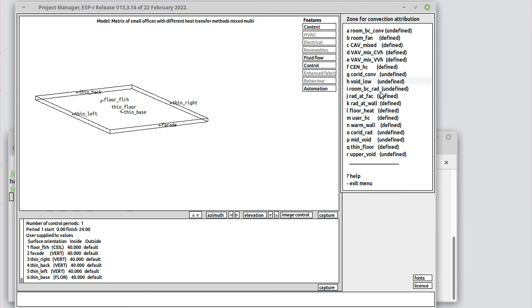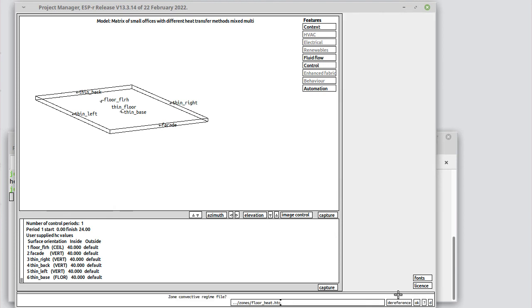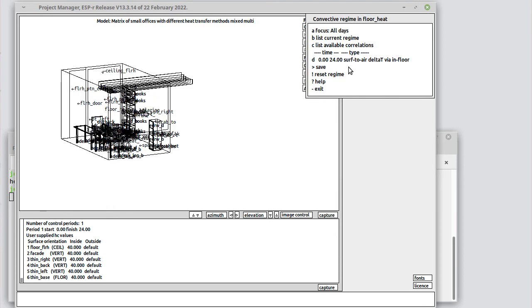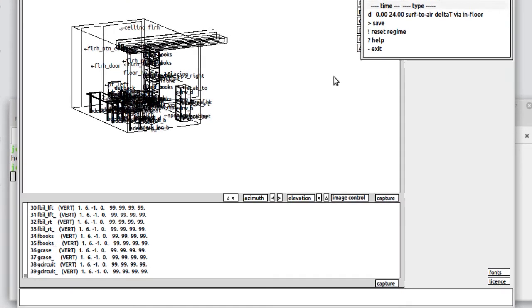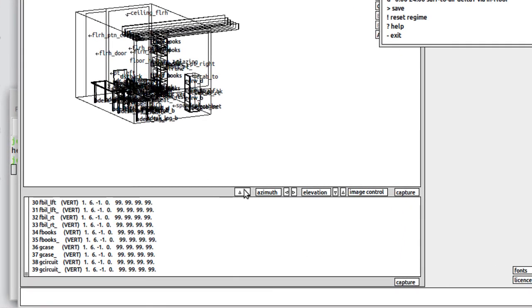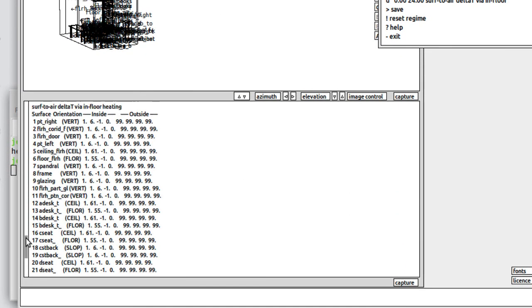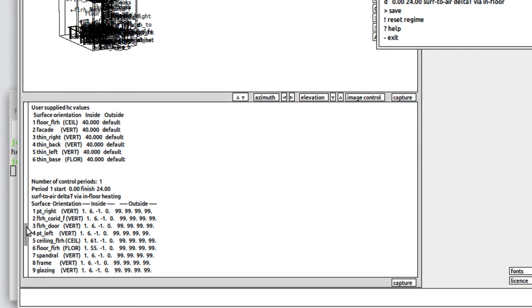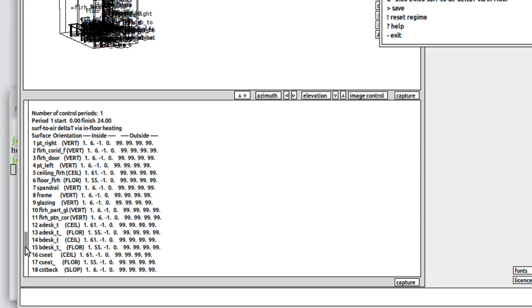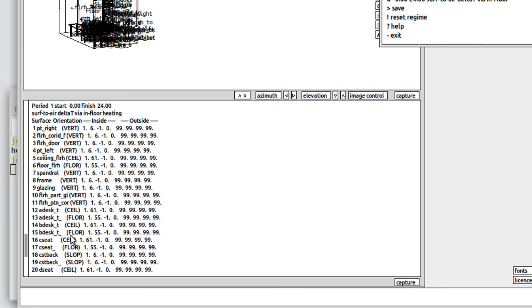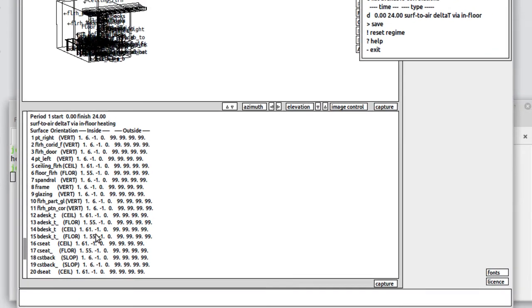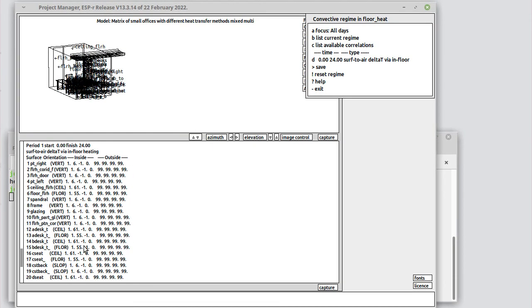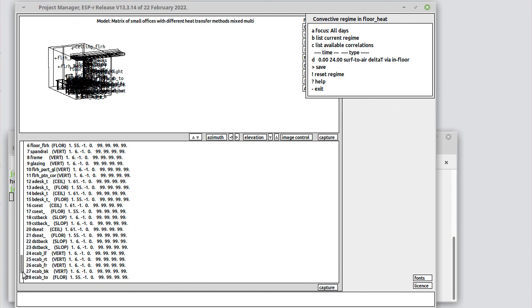If we go into the floor heating room, there's also a heat transfer coefficient defined. And there the current regime involves a surface to air delta T by way of in-floor heating. There's a particular correlation that's related to that and each of the surfaces in the zone gets a relevant set of attributes to direct the simulation to use specific kinds of heat transfer as the simulation progresses.